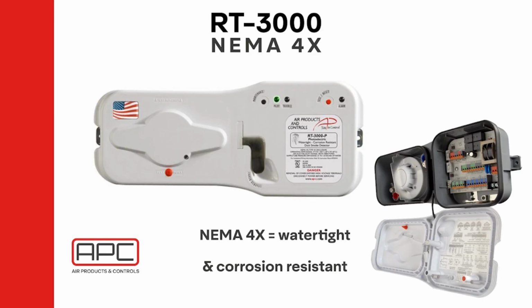The RT3000 is a conventional 4-wire NEMA 4X rated weather-tight duct smoke detector. As with the standard duct smoke detectors, the RT features photoelectric heads. The RT is the HVAC industry's first and only NEMA 4X rated self-enclosed duct smoke detector. It is watertight and corrosion resistant, perfect for coastal applications or corrosive environments such as where acid rain is present.